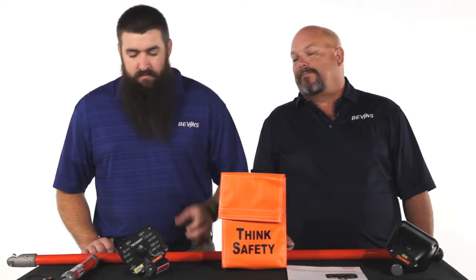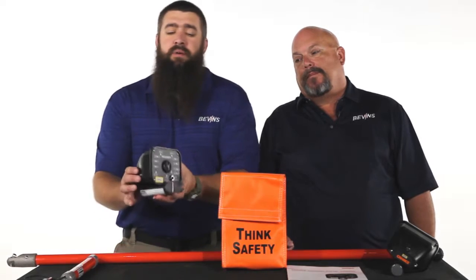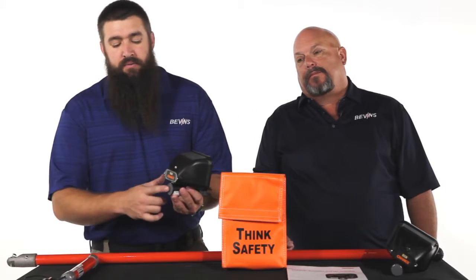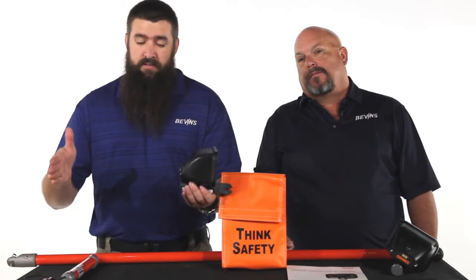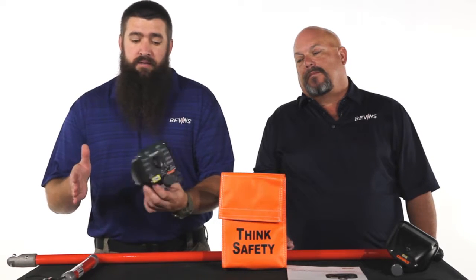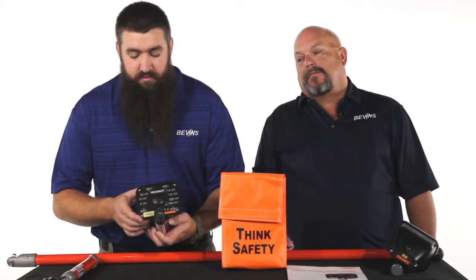All right, Casey, now that we've tested, let's take them through what they're going to see on the dial face and what those indications mean. So basically, the way the proximity indicator works is our input sensor is brought in close proximity to an energized conductor. The closer it is brought in, the higher the indication we'll see on screen.